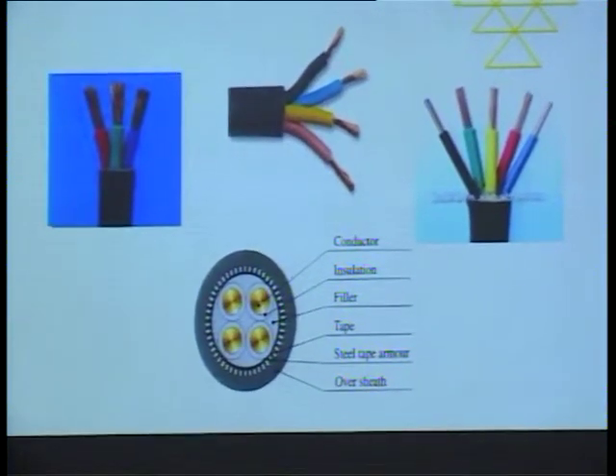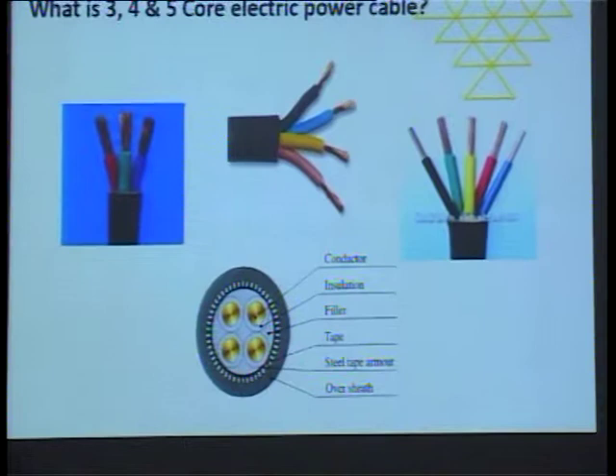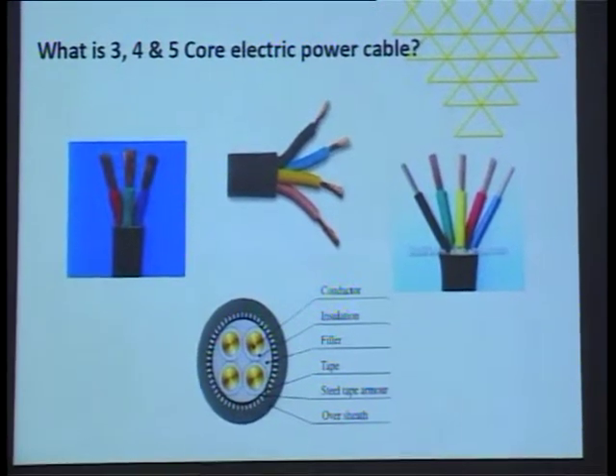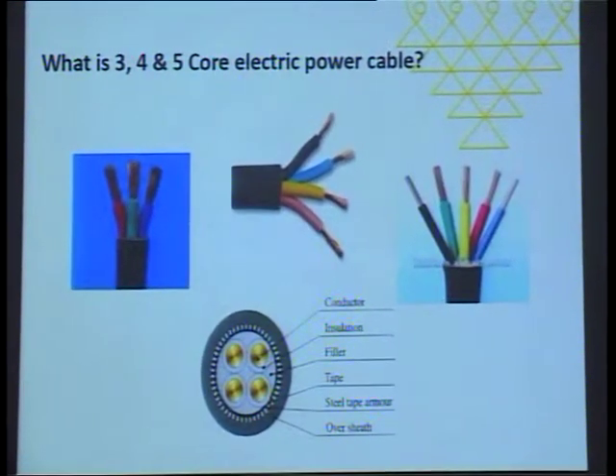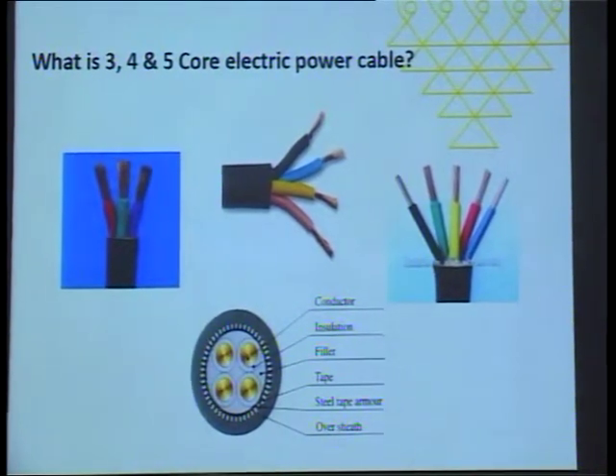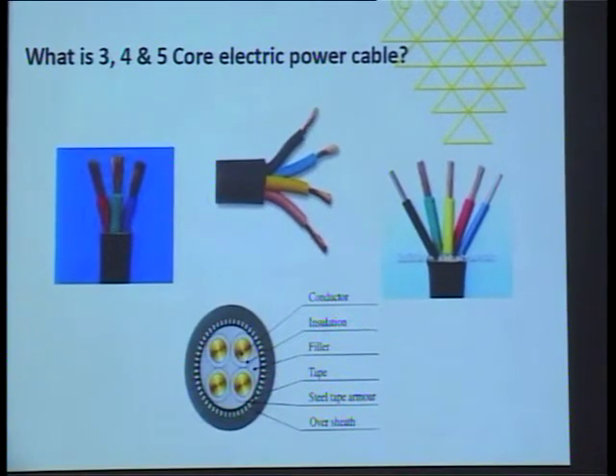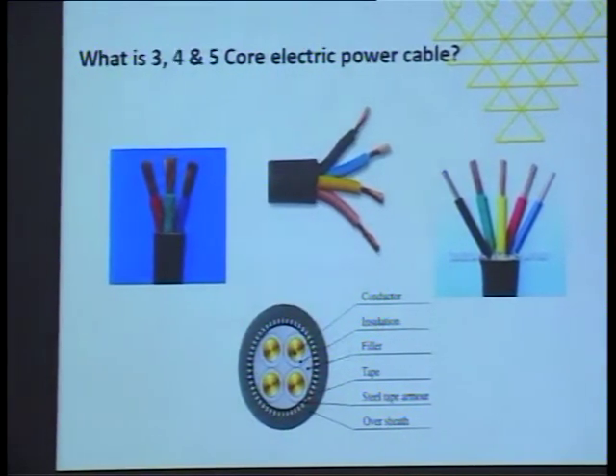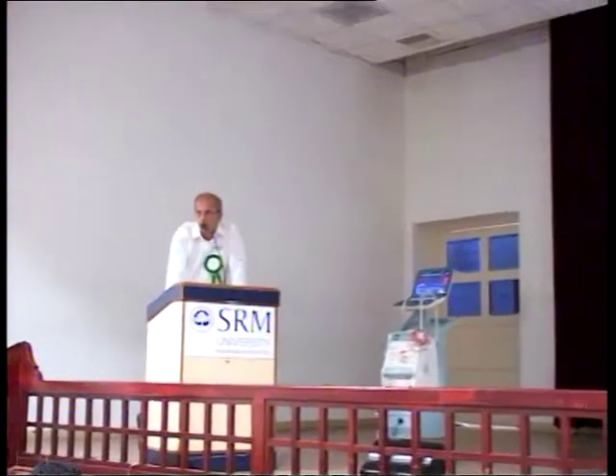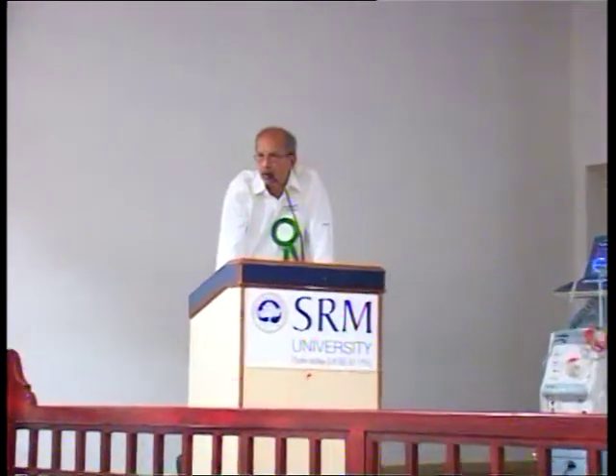So you can't use simple wires which are used at your residence, because they are designed for very low current capacity. For high power connections, you require special types of cables, and these cables are available in 3-core type. 3-core type cables are typically what we use for domestic purposes, or at the most for currents going up to 15 amperes. But if you are connecting a very heavy load, then probably you will require a 4-core cable or a 5-core cable.